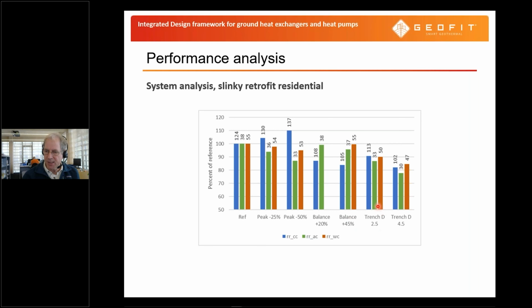And we've looked, for instance, at the trench, the distance between the different trenches that we need to install the slinky, because one trench is usually not enough. So if we have a distance between the trenches of 2.5 meters, or a distance between the trenches of 4.5 meters, here you can see the relative effect of all those parameterizations.